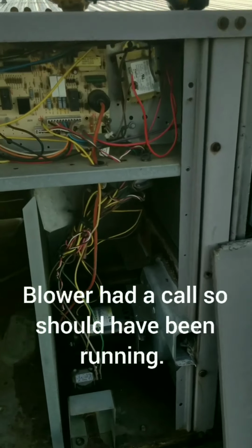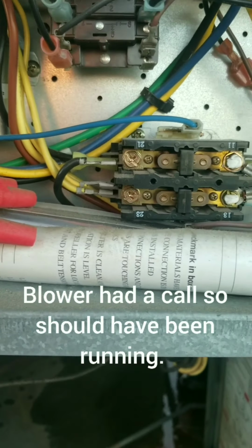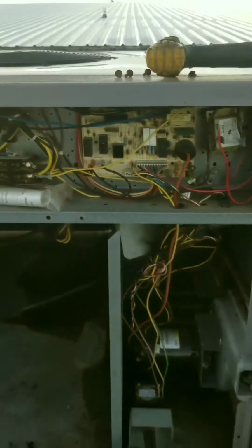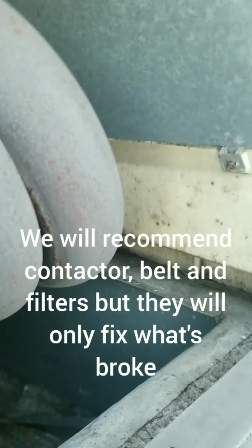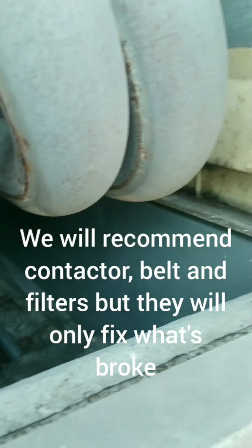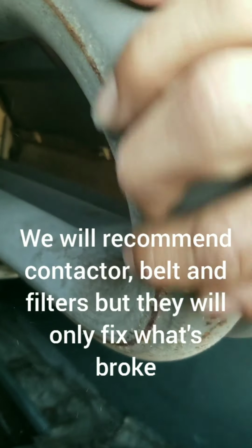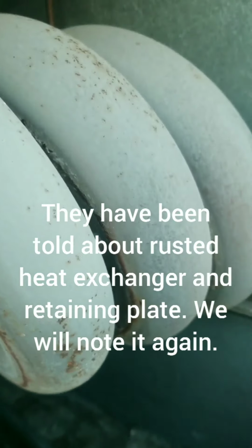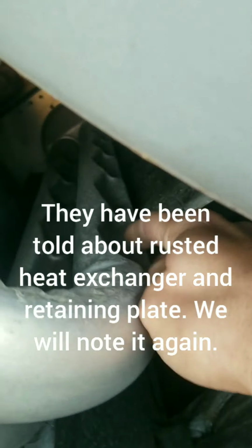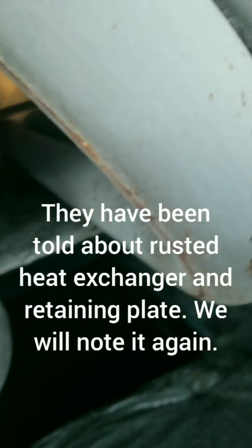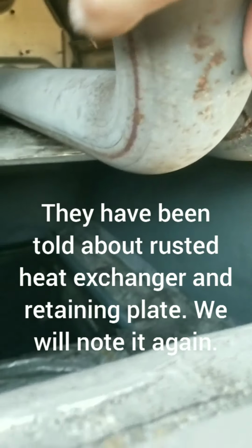The blower's not hot, so we've either got open windings or a relay not sending power. So we'll have to investigate that. Heat exchanger doesn't look great. Got some rust. These seams are the first thing that'll crack. Seams and these indentions here, which I don't see anything on the indentions, but these seams don't look great. I'll bet we've got a few soft spots in there.